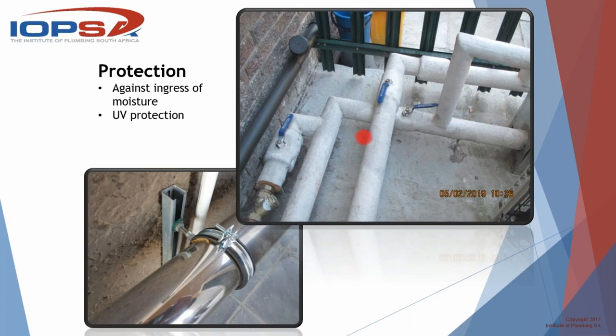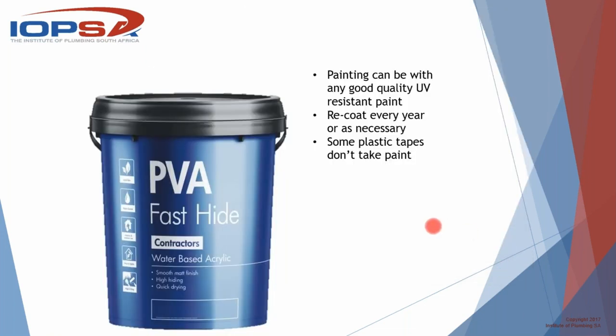All right, but you cross that bridge when you get to it. In terms of, you know, if the thing's done properly, it's going to last 10 years. And then after that, you can budget for another layer of lagging. So you've got to protect it. Now, what do we do in Mrs. Jones' domestic situations? Well, the easiest for me has always been to paint. I use 100% acrylic PVA, not this particular one, but any very, very good quality PVA. I wouldn't go for a low quality paint, because that's not really going to do much, or perhaps a roof paint, or some kind of a paint that has got a little bit of elasticity to it, that is UV stable.